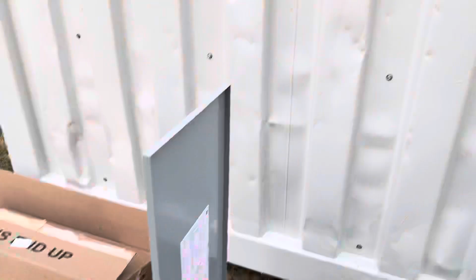I will also be installing a 200 amp breaker inside this panel that will feed the interior panel. That's going to be my grid panel feeding all my inverters. And then from the output panel on the inside, which won't be the solar output, it'll just be the power output from the transformer, is going to feed in to one of the line sides on this transfer switch.